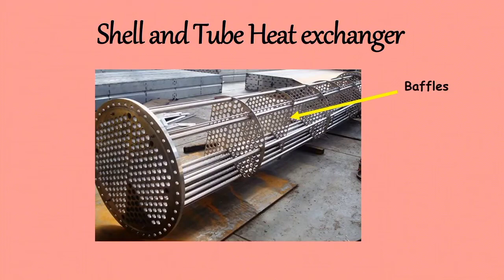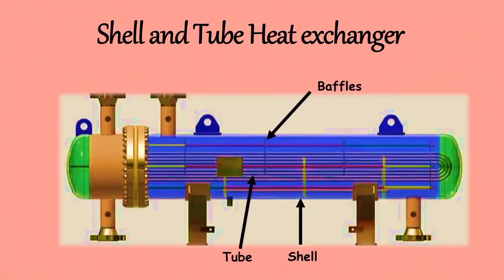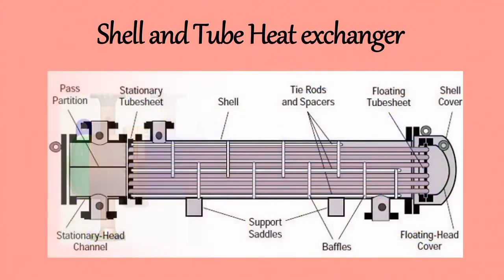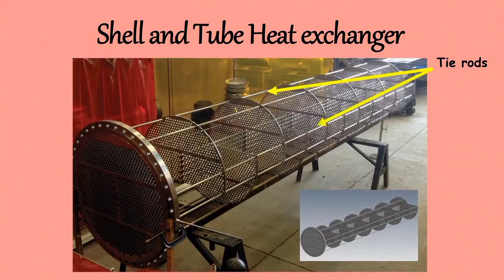The last component is Tie rods. Tie rods are used to hold the baffles in place with spaces to position or locate the baffles. Tie rods are fixed at one end in the tube sheet by making blind holes. Usually 4 to 6 tie rods with at least 10 mm diameter are necessary.